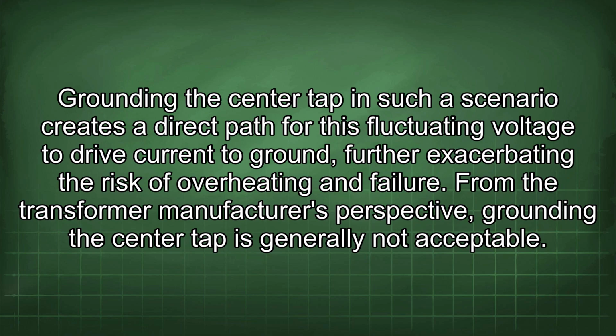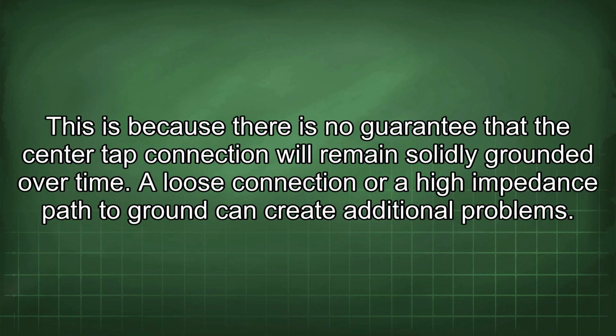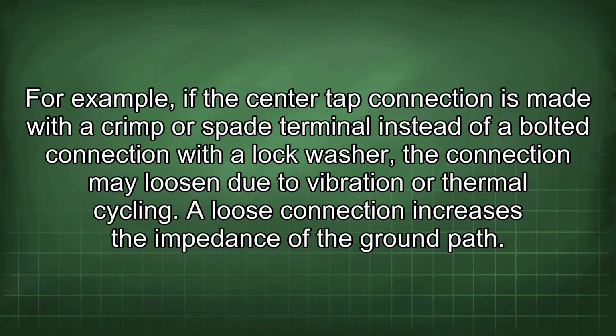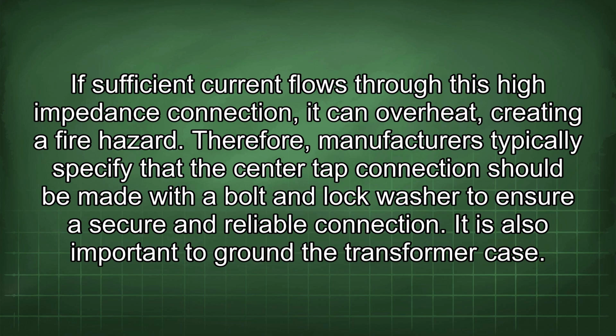From the transformer manufacturer's perspective, grounding the center tap is generally not acceptable. This is because there is no guarantee that the center tap connection will remain solidly grounded over time. A loose connection or a high impedance path to ground can create additional problems. For example, if the center tap connection is made with a crimp or spade terminal instead of a bolted connection with a lock washer, the connection may loosen due to vibration or thermal cycling. A loose connection increases the impedance of the ground path. If sufficient current flows through this high impedance connection, it can overheat, creating a fire hazard. Therefore, manufacturers typically specify that the center tap connection should be made with a bolt and lock washer to ensure a secure and reliable connection.